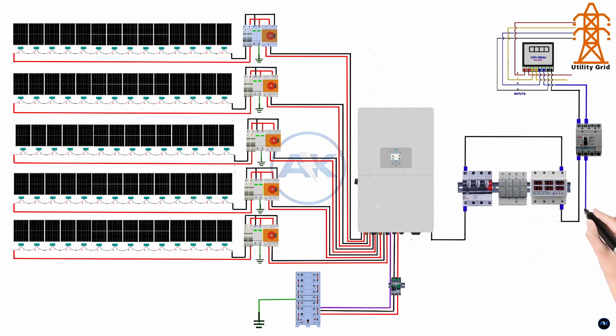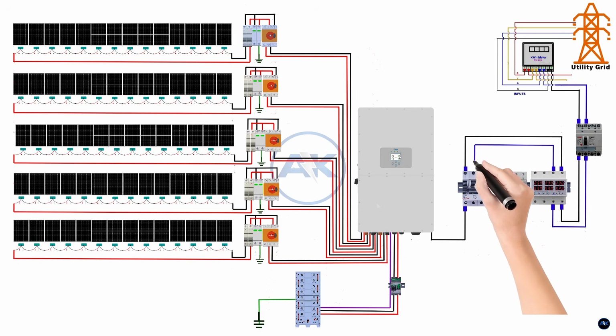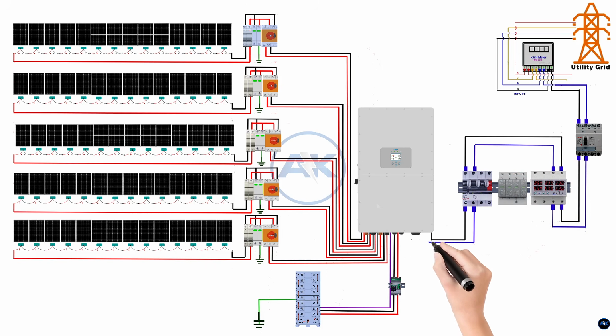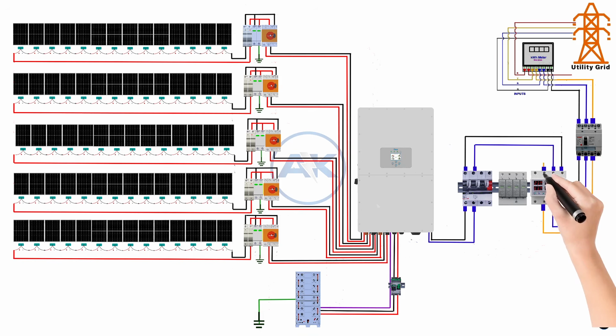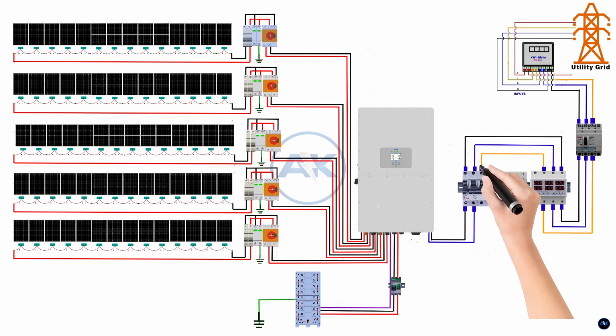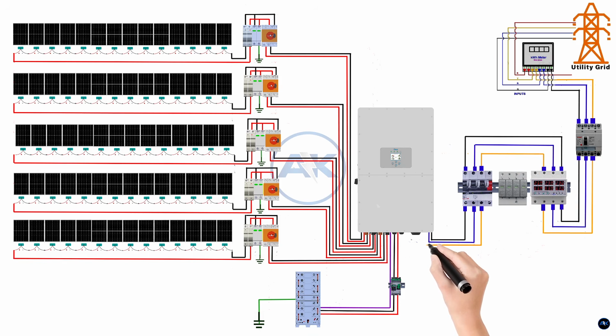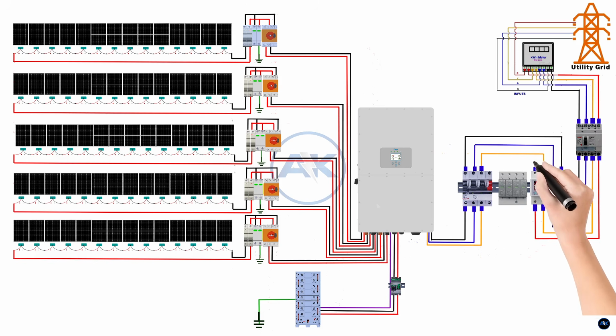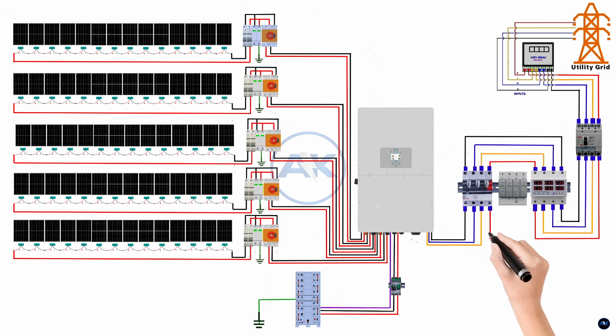From the output side of the meter, run the same L1, L2, L3, neutral, and ground cables toward the inverter protection devices. Next is the AC isolator. The AC isolator allows you to safely disconnect the inverter from the grid for maintenance or emergencies. Use a three-phase AC isolator rated for at least 400 volts AC and a current rating suitable for the inverter, typically 63 to 100 amps.